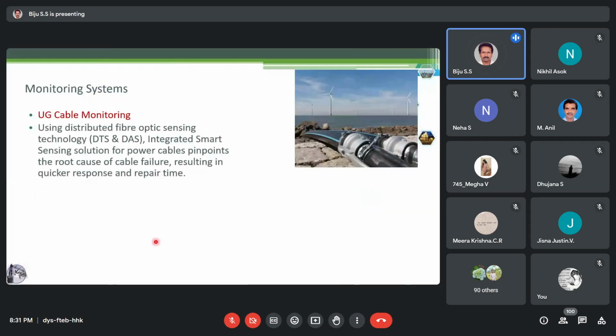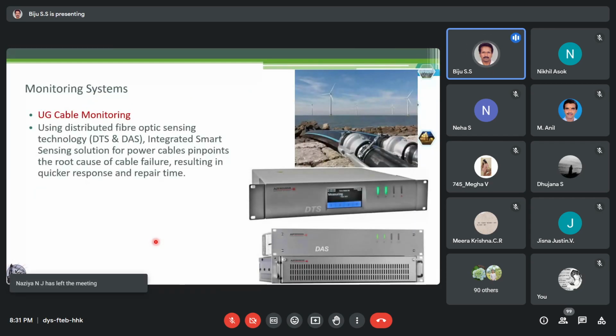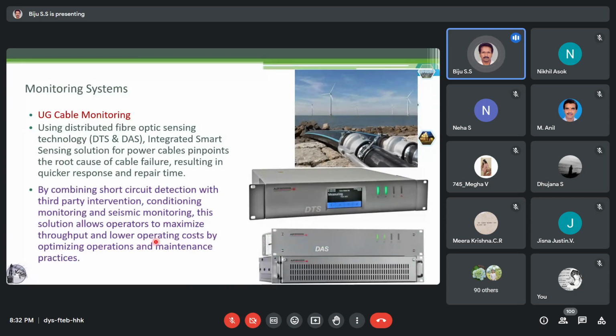And again, nowadays we can monitor the cables also. Earlier, it was very difficult to monitor underground cables, but now with distributed fiber optic sensing technology, distributed temperature systems and distributed acoustic systems, we can continuously monitor the healthiness of the cables. It can be integrated with other things like intruder and third-party intervention. When somebody digs into the cable route, it can detect it and give an alarm to the operator, to the field staff.